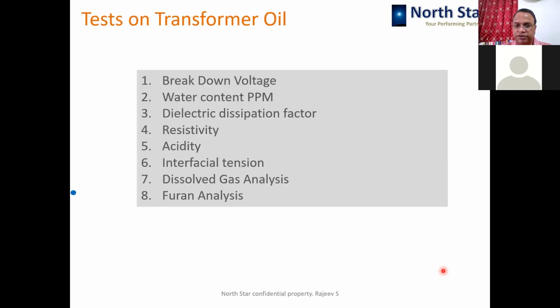Then oil, when we say oil, we can do a number of tests on the transformer, starting from breakdown voltage to furan analysis or DGA. DGA and furan analysis are diagnostic types of tests, so they need not be repeated or performed as a routine activity unless there is a necessity. Okay, but breakdown voltage, ppm, dissipation factor, resistivity, acidity, interfacial tension, these tests are to be performed not every 6 months or every year, but at least once in 2 years or once in 3 years.